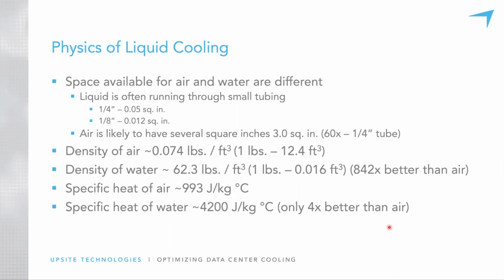I mean, it's absolutely true that liquid is a better medium for carrying away heat than air, but it's not as good, and air is not as bad as a lot of the hype. One of the numbers that I hear often thrown around is that air can only handle up to 20 kilowatts in a cabinet. And I know of a number of facilities that are doing 40 plus kilowatts in a cabinet with air. There's some extreme setup that's required for that, but it is possible to cool a lot more than 20 kilowatts in a cabinet with air. It does present challenges. So liquid definitely has its advantages.